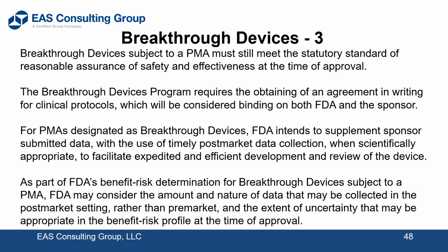The shortcuts come from FDA being informed beforehand, knowing what's coming, expediting the review process, maybe even putting you a little more ahead of the line if it has a serious impact on patient safety if it's implemented, positive patient safety. And you notice here in the last bullet point or last paragraph, also they'll be wired in on a post-market surveillance, if you will.